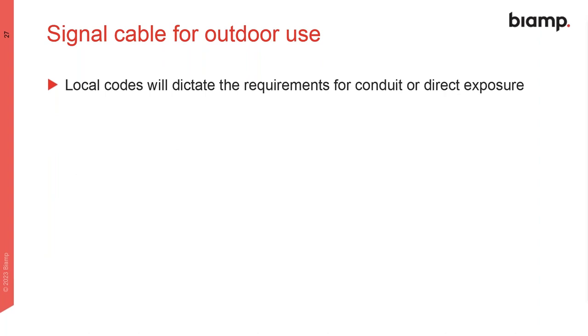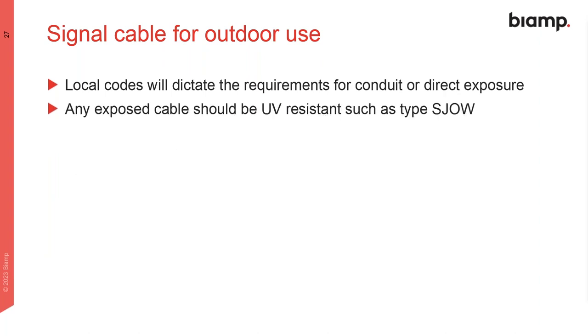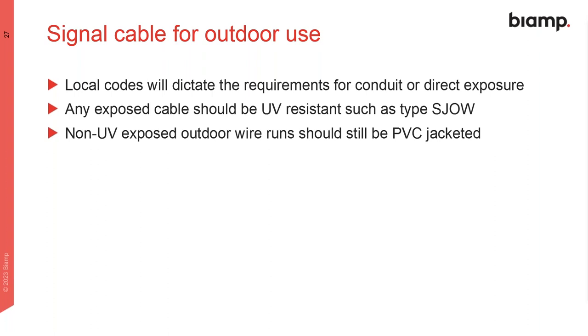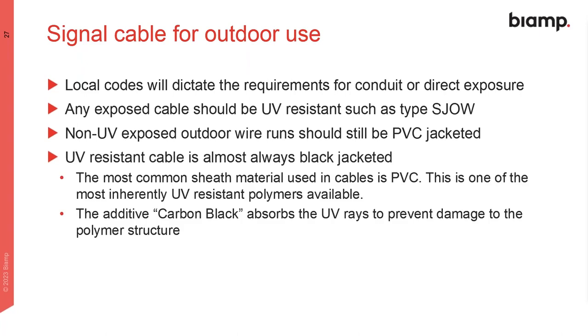Local codes ultimately are going to dictate the requirements for conduit or direct exposure cables. Any exposed cables should be UV resistant, such as SJOW. Anything light colored, cream colored, white colored, there's a good chance that it's not UV resistant in a plain old PVC jacket. Let's try and get our black jacketed UV resistant cable.